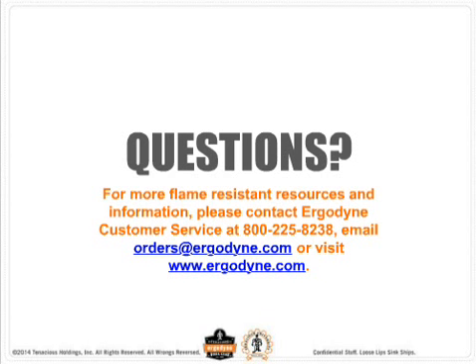I would assume if anyone is within the boundary of an arc flash after you've performed your hazard risk assessment, whether that be maintenance workers, whether they're in there for 2 minutes or 20 minutes, then they should be wearing the appropriate PPE if they are within what's called the arc flash boundary. I don't know the specifics of this situation, but I would say yes, if they are performing some work within that arc flash boundary, then they should be wearing the appropriate PPE at whatever HRC level is required within that boundary.